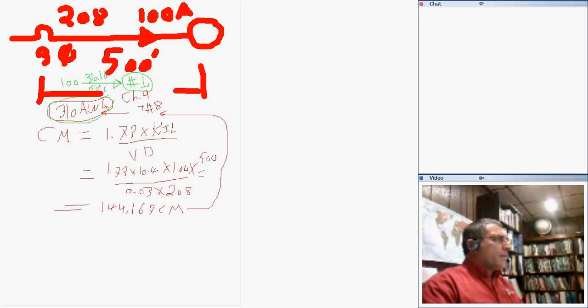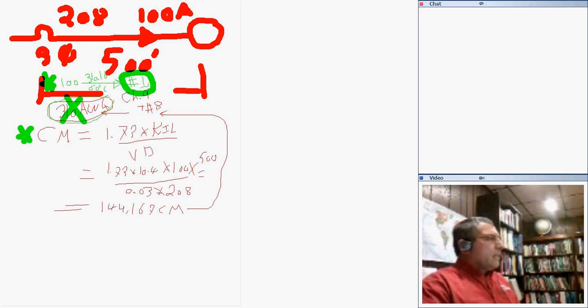So if you guys are, I did number 1, I sized based on 100 amp, and number 2, I sized based on circular mil, and I picked up the size. As you can see, the size that can get me the largest conductor. So I have to use the 3 aught. Here, I picked the conductor. There you go. Picked up the 3 aught conductor because it's the largest conductor. So I wouldn't use that number 1.